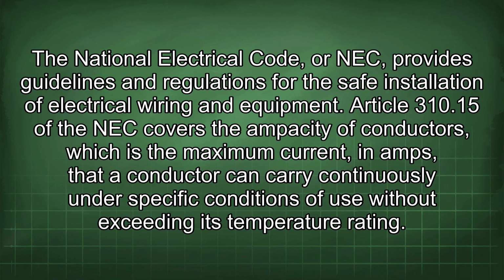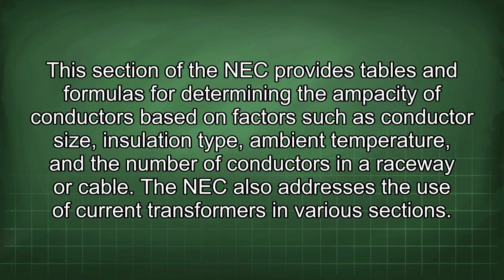The National Electrical Code, or NEC, provides guidelines and regulations for the safe installation of electrical wiring and equipment. Article 310.15 of the NEC covers the ampacity of conductors, which is the maximum current, in amps, that a conductor can carry continuously under specific conditions of use without exceeding its temperature rating. This section of the NEC provides tables and formulas for determining the ampacity of conductors based on factors such as conductor size, insulation type, ambient temperature, and the number of conductors in a raceway or cable.